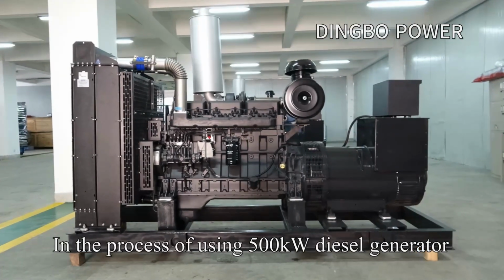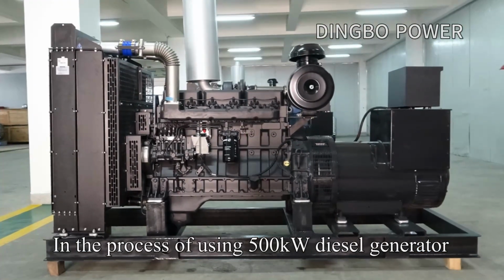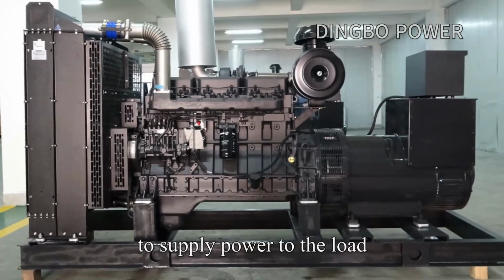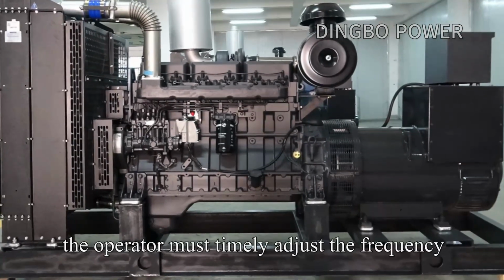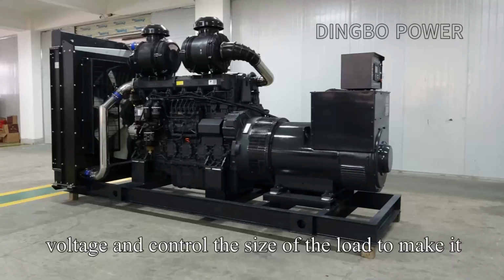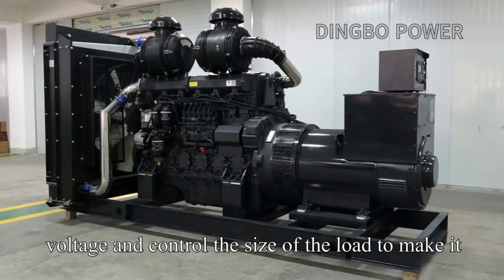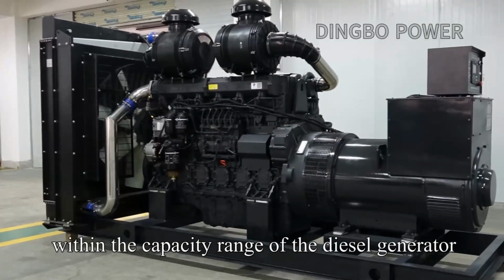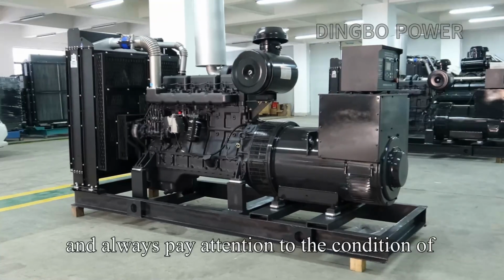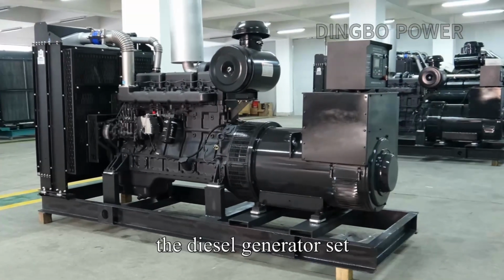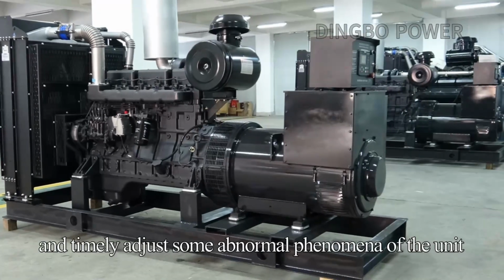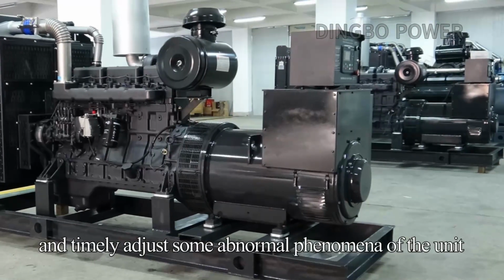In the process of using a 500 kilowatt diesel generator to supply power to the load, the operator must timely adjust the frequency and voltage, and control the size of the load to keep it within the capacity range of the diesel generator, always paying attention to the condition of the unit and timely adjusting any abnormal phenomena.